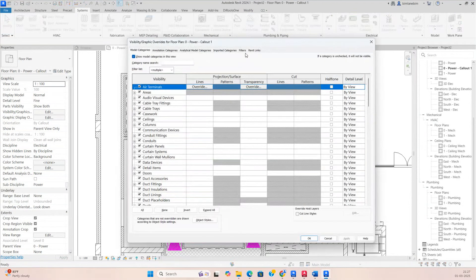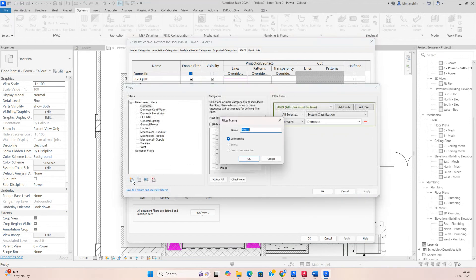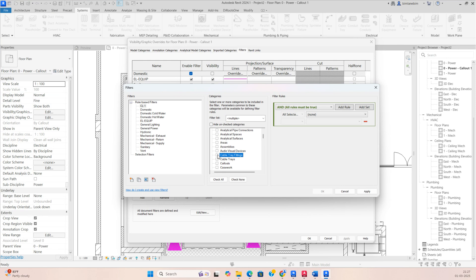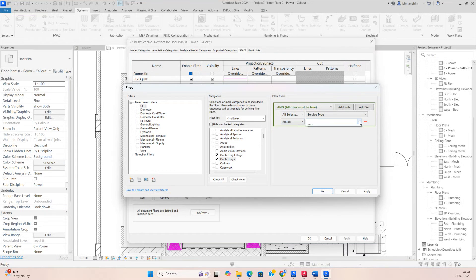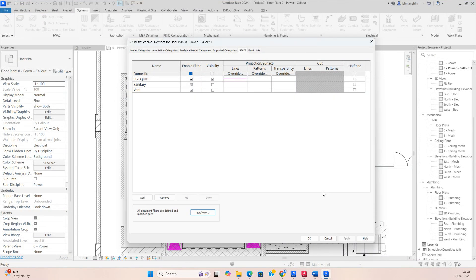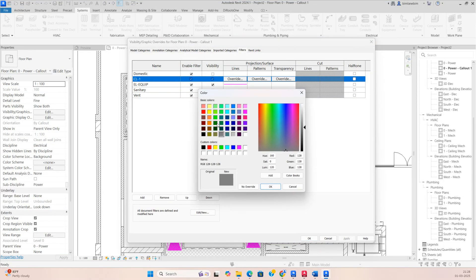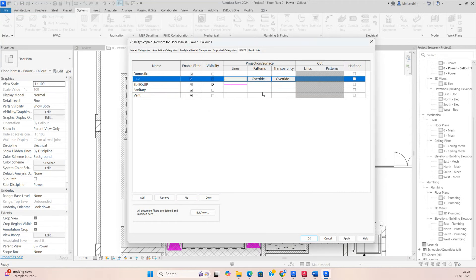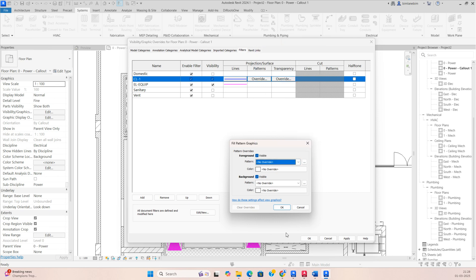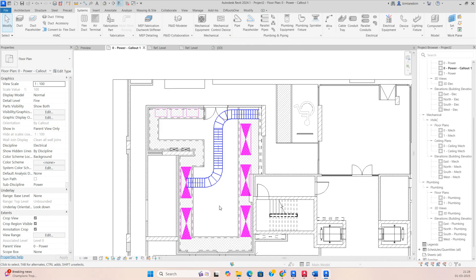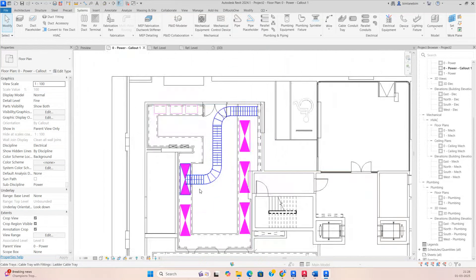Go to VV > Filter and add a filter for cable ladder — call it CL1. Select Cable Tray and Cable Tray Fittings, then set the parameter to Service Type, equals CL1. Add it, then set a color — I'm using blue with solid fill. Click OK and you can see the cable ladder appears in that color.